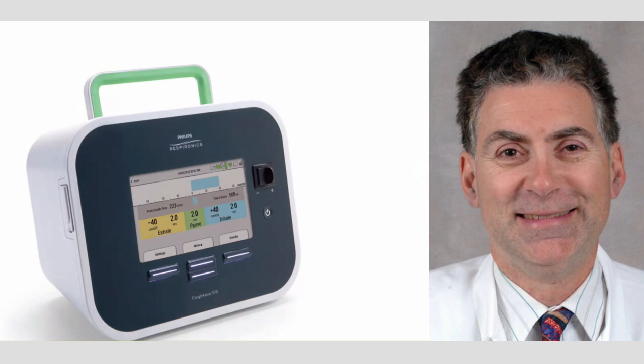I convinced Mr. Emerson to make this device in 1988, and we started using it immediately in critical care. However, I said that this machine was like the old one in that it goes to 40, and it should be used at 40. However, the CoughAssist was calibrated in millimeters of mercury, and 40 millimeters of mercury is 54.1 centimeters of water. So because I said it should be used at 40 centimeters of water, it's been used wrongly ever since it's been on the market.